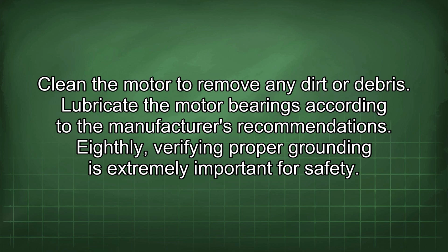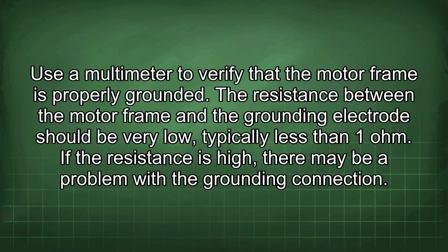Eighthly, verifying proper grounding is extremely important for safety. Use a multimeter to verify that the motor frame is properly grounded. The resistance between the motor frame and the grounding electrode should be very low, typically less than 1 ohm. If the resistance is high, there may be a problem with the grounding connection.